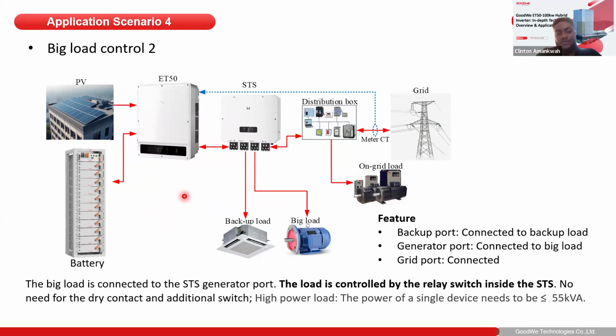Now, the second applicable scenario under the fourth application is the connectivity of a big load on the generator port. Like I said, the diesel generator port can be used for multifunctional purposes. One is the default use, which is the connectivity of the diesel generator. The other functionality is connectivity of a big load. So instead of connecting your big load to the backup ports, where you will have to introduce a contactor to make sure this big load doesn't drain much of your battery, you can also connect this big load to the generator port directly, in the absence of a diesel generator.